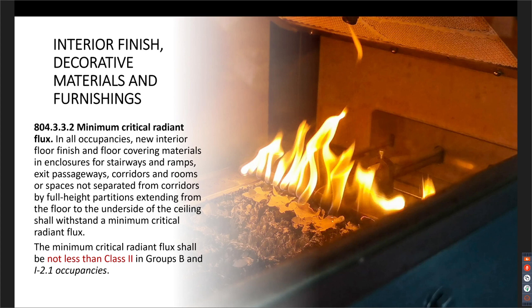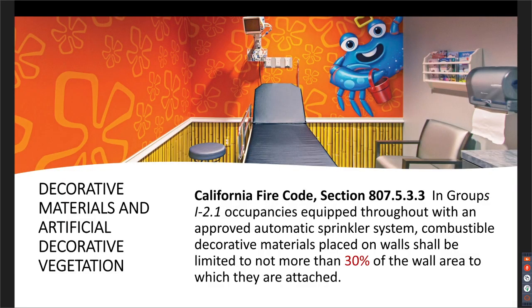There's requirements for flooring and the critical radiant flux class that the flooring can be, make sure that meets. There's limitations for how much the wall can be covered with decorative materials. These allowances differ between 101 and building code. So if you participate with CMS, please make sure you also meet the NFPA 101 requirements.